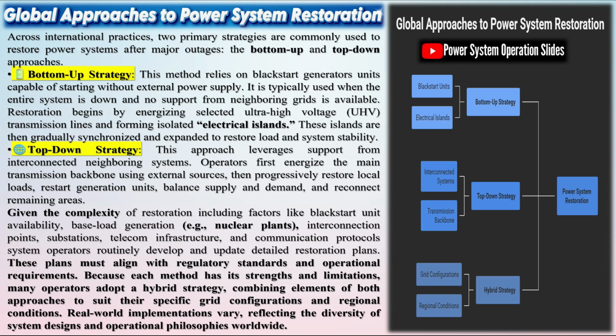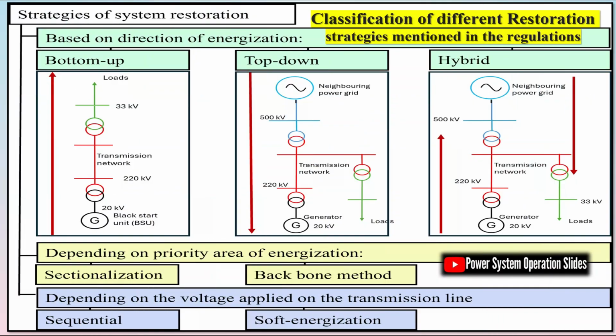This requires establishing cranking paths between black start sources and target stations. TNSPs and distribution companies then disconnect circuits and re-energize the transmission network with sufficient load to maintain voltage and frequency stability. Full restoration depends on available generation and the capacity of distribution networks to absorb load.